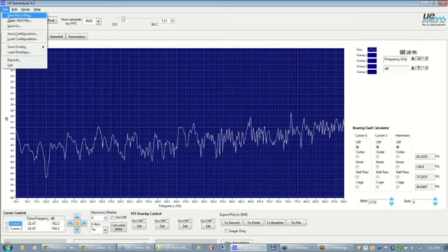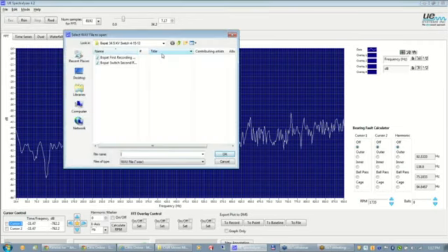So we'll go ahead and start with the FFT and a wave file from a customer of mine in Maryland. And in this particular recording, it was on a 34 kV switch, and there are 2 different recordings here. An initial recording that the technicians made on a first-year visit, and a subsequent recording that was done approximately 6 months later. One thing I stress to our guys is what we hear in the ultrasound should be an indicator, but it's never a definitive, concrete assessment of what's going on.